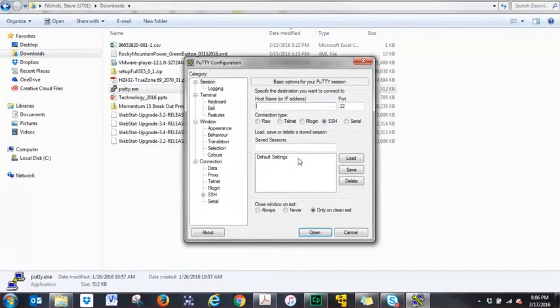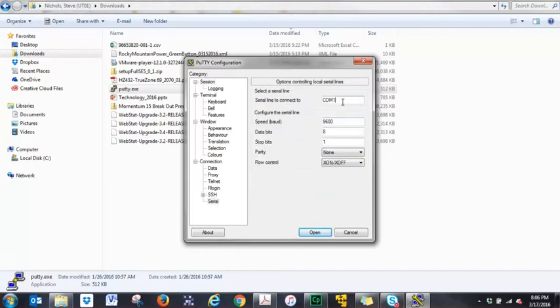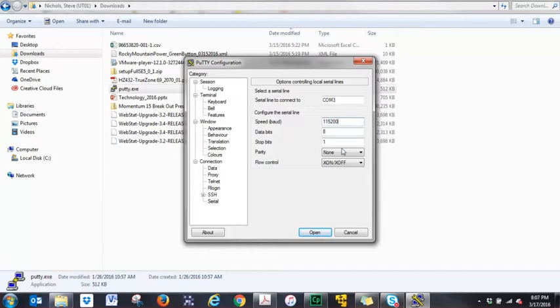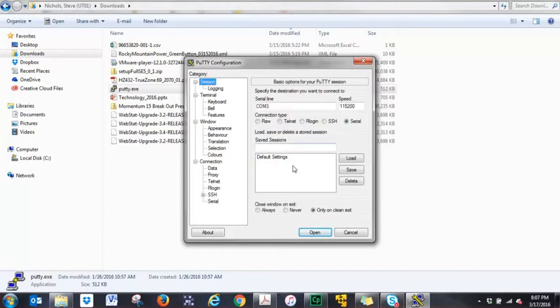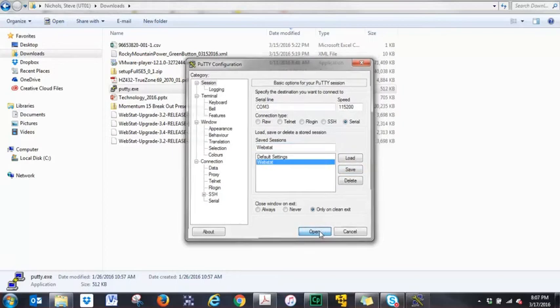And choose Run. Now once you're here, you have to configure it so it can talk to your Webstat. So the first thing you want to do is click on Serial. And then click on Serial down here and change your COM to COM3. This is the adapter COM port that you have plugged in. Next, change the speed to 115200, eight data bits, one stop bit, none parity, and none on flow control. Go back to Session, type in Webstat to save your session so the next time you open up Putty you don't have to enter in all the details. You just click on Webstat, choose Webstat and open.